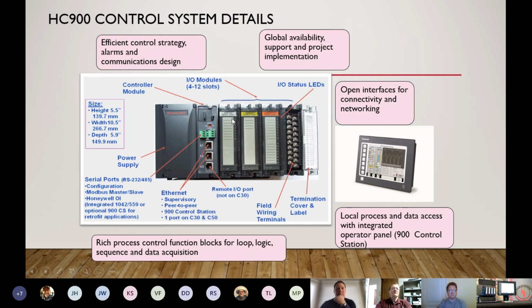We have several different flavors of input and output boards. We have analog input boards, which are universal, which means on the same board you can have a thermocouple, an RTD, 4 to 20, 1 to 5 volt, all on the same board and configured for your application. That's pretty unique in the industry. Typically in the PLC world, you'll be ordering a board for specific analog inputs. In this controller, it's universal. Honeywell kept that same theme when they came out with the UDC controllers, universal digital controller, which allowed for universal analog inputs, and they carried that forward into the HC900.